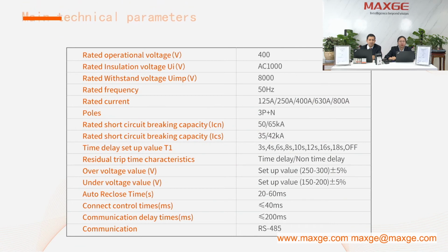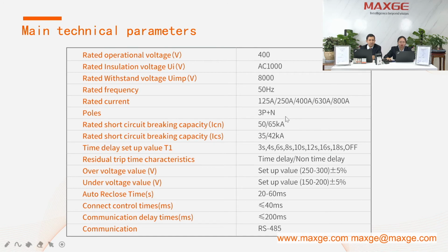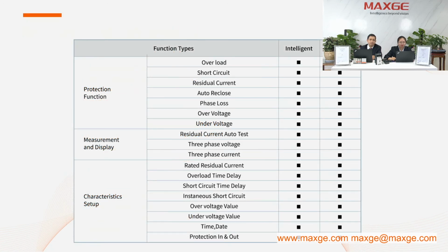And these are the specifications of the smart MCCB. We also have the high breaking capacity. And here the communication is normally RS485, which is the industrial standard. Yes. Here we have the function types with the protection function, measurement and display, and characteristics setup.